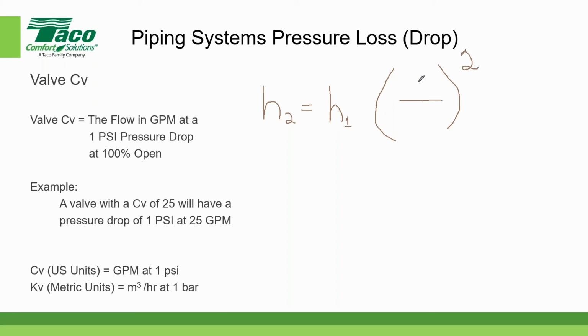So if the CV of the valve was equal to 35, then it would have a 1 pound pressure drop at 35 gallons per minute, PSI. So if we dropped the flow through that valve to 17 gallons per minute, then it would be 17 divided by 35, squared.